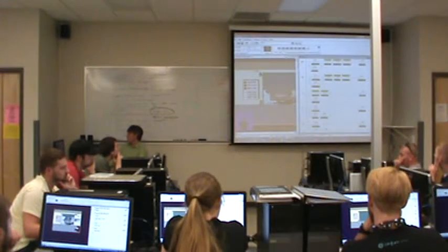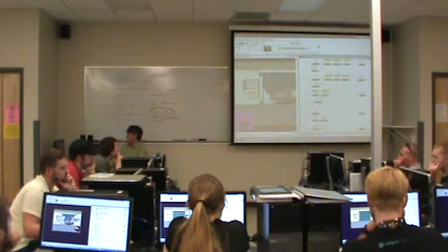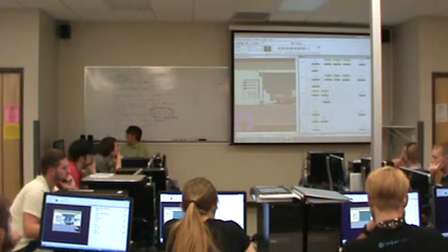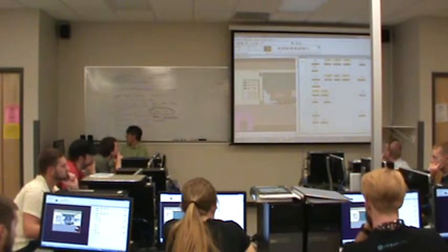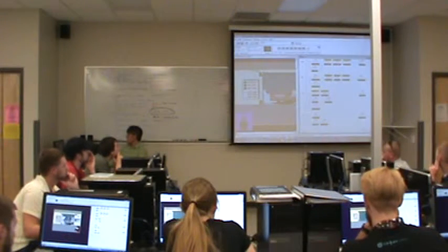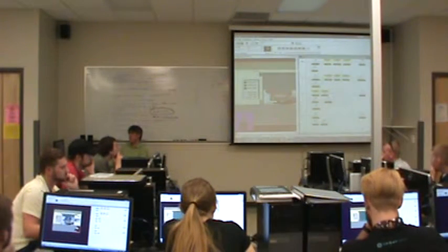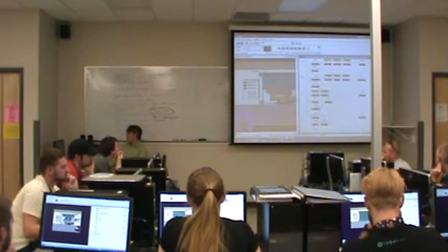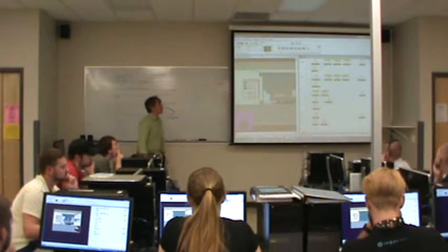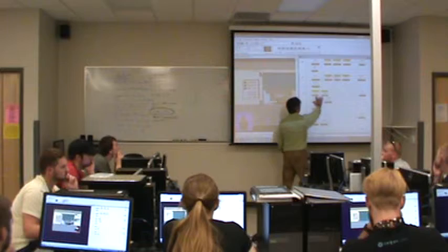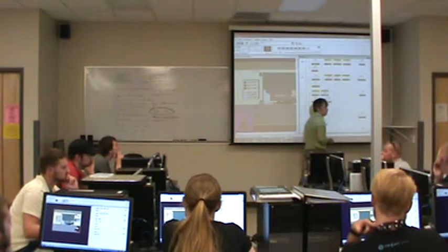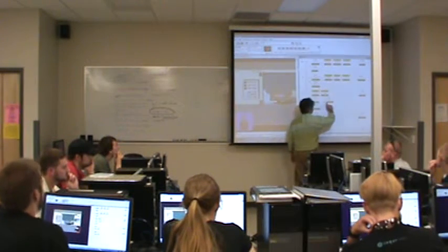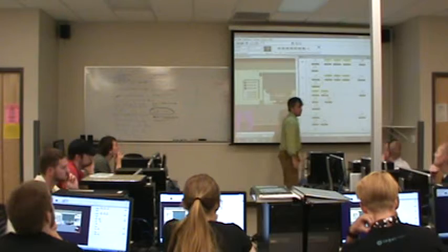Now the way I'm going to do this is I have to add one more OR condition. If the motor is moving up, or the motor is moving down, then I would want this to flash. Make sense? If we are between the upper and lower limit, then these two will be true, and the ajar lamp will be on solid. If the motor is moving up or the motor is moving down, then quick flash should happen and the ajar lamp will flash. Okay? Do you see any problem with this?